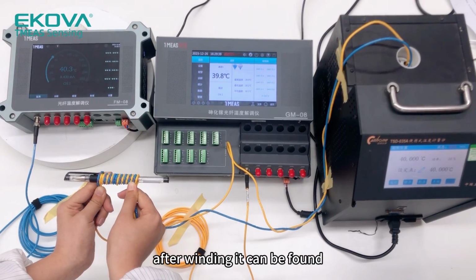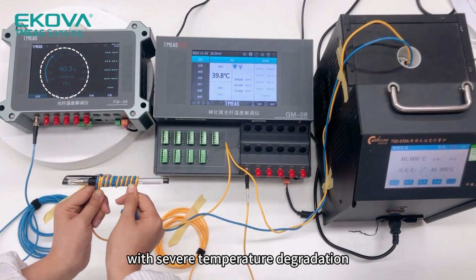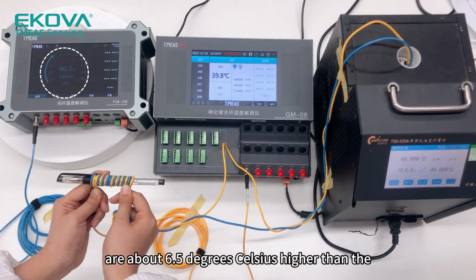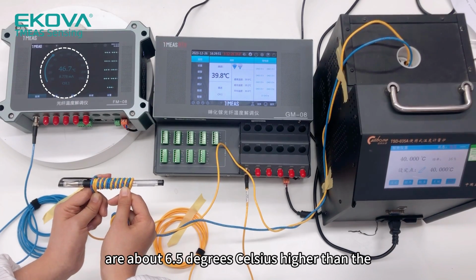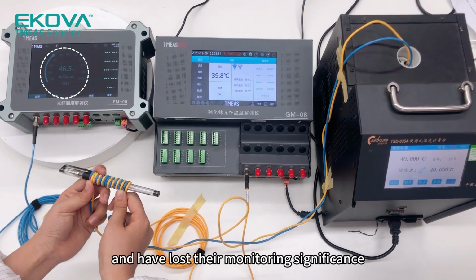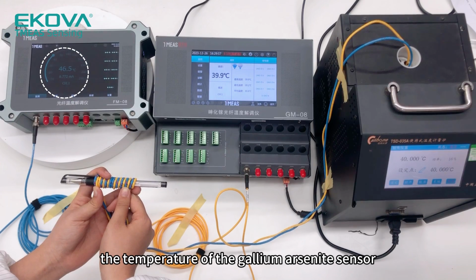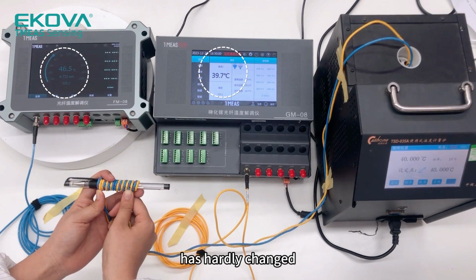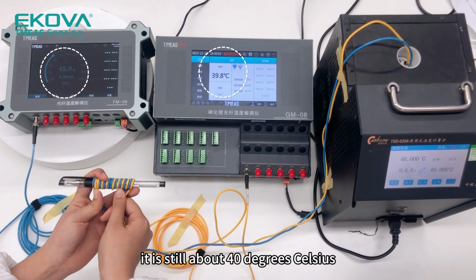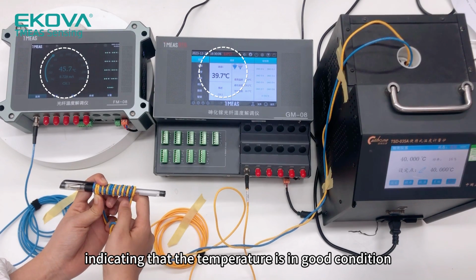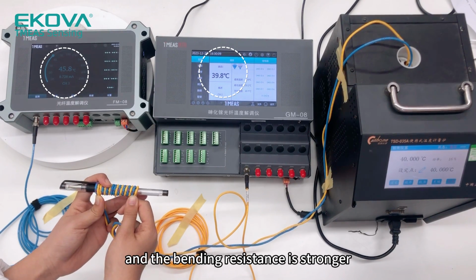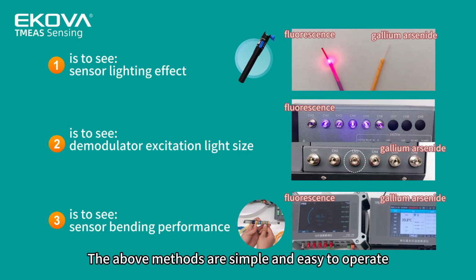After winding, you can find the fluorescent sensor with severe temperature degradation reads about 6.5 degrees Celsius higher than the actual temperature and has lost its monitoring significance. The temperature of the gallium arsenide sensor has hardly changed. It is still about 40 degrees Celsius, indicating that the temperature is in good condition and the bending resistance is stronger.